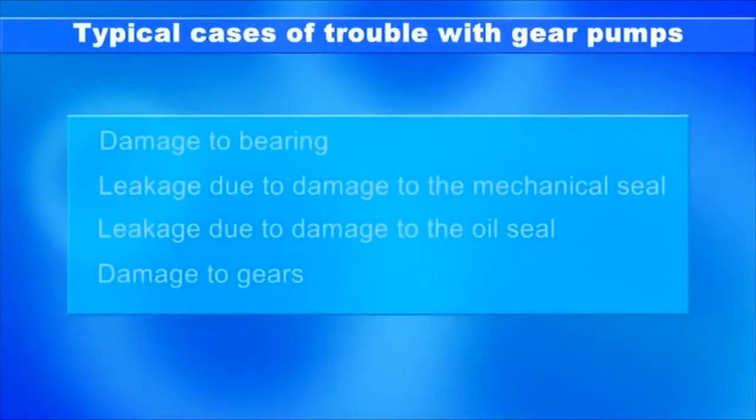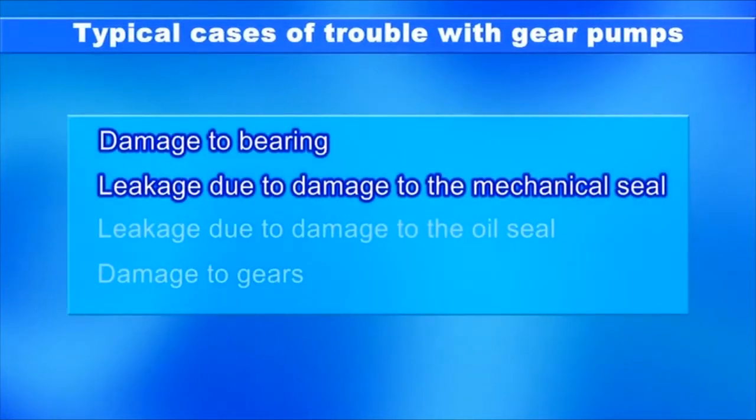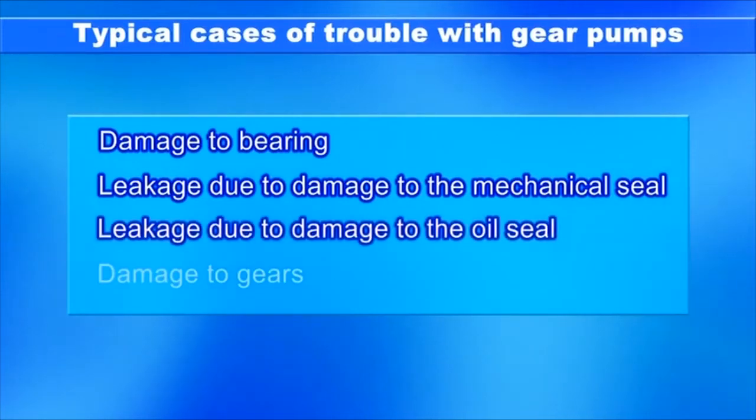The following cases of trouble with gear pumps have been reported: damage to the bearing, leakage due to damage to the mechanical seal, leakage due to damage to the oil seal, and damage to the gears.